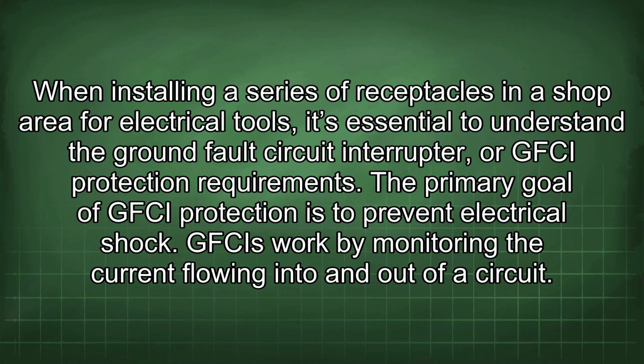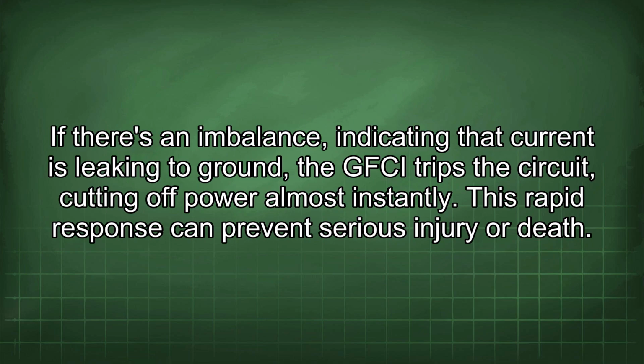When installing a series of receptacles in a shop area for electrical tools, it's essential to understand the ground fault circuit interrupter, or GFCI, protection requirements. The primary goal of GFCI protection is to prevent electrical shock. GFCIs work by monitoring the current flowing into and out of a circuit. If there's an imbalance, indicating that current is leaking to ground, the GFCI trips the circuit, cutting off power almost instantly. This rapid response can prevent serious injury or death.